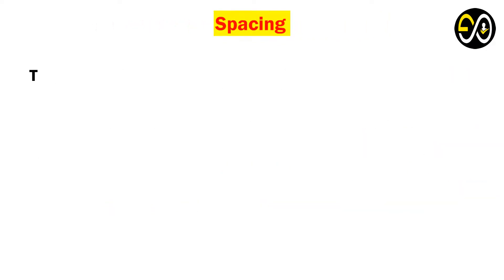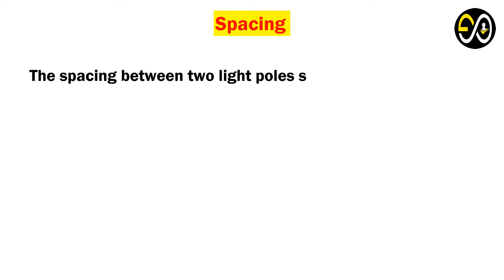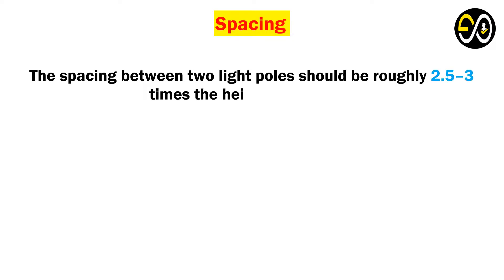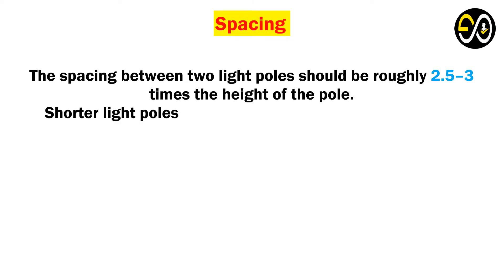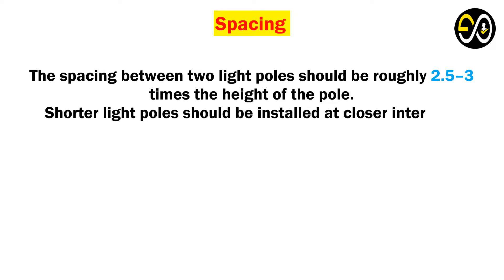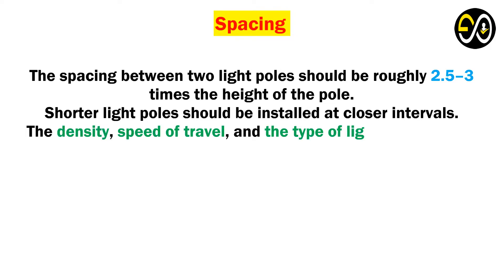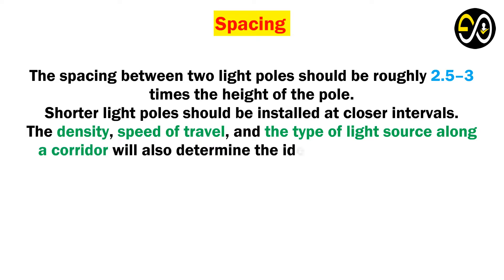The spacing between two light poles should be roughly 2.5 to 3 times the height of the pole. Shorter light poles should be installed at closer intervals. The density, speed of travel, and the type of light source along a corridor will also determine the ideal height and spacing.